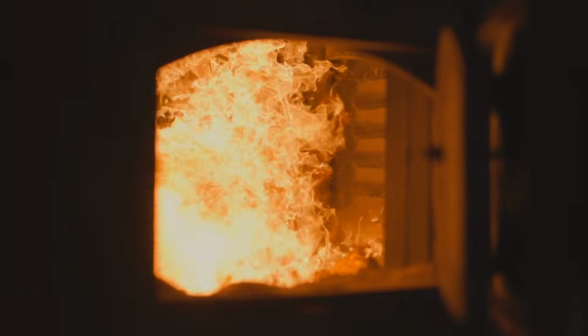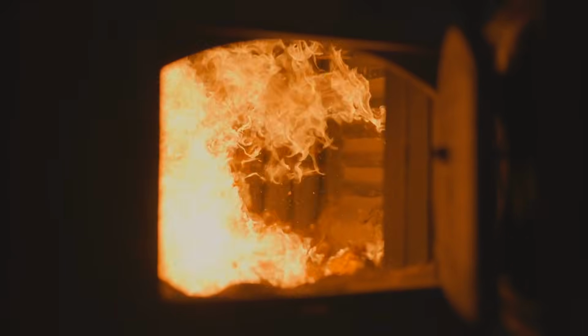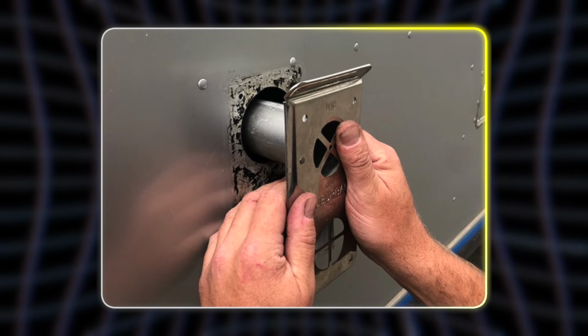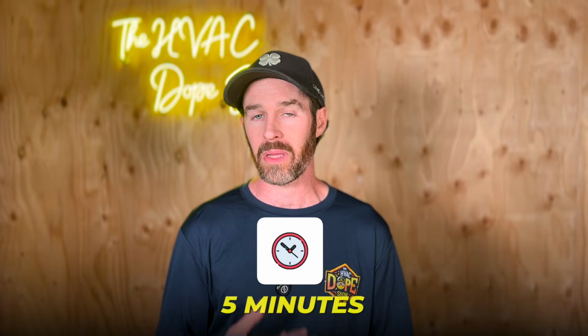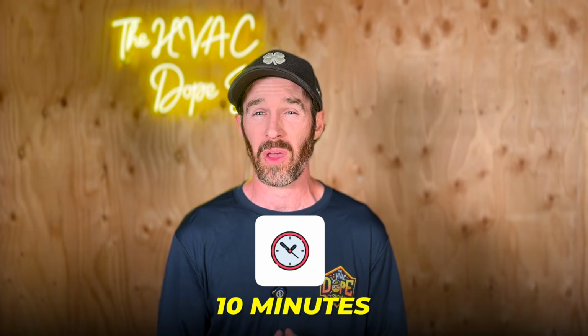So now that you understand how heat exchangers work in terms of the fire from the combustion processes going into these tubes or into the heat exchanger combustion chamber, what happens when there's a crack is that essentially you're running a risk that there is carbon monoxide or exhaust gases leaking from the heat exchanger into the airstream. And so what this means is that when the furnace is running, after maybe 5 minutes or 10 minutes, or maybe right away, if you have a really bad crack in your heat exchanger, it will start dumping exhaust gases into your home.